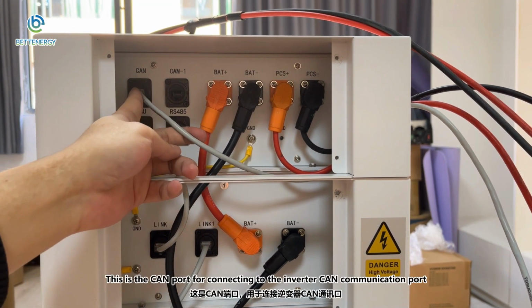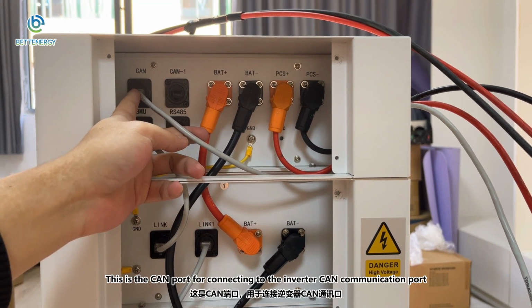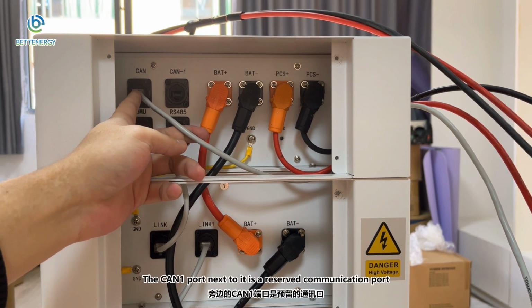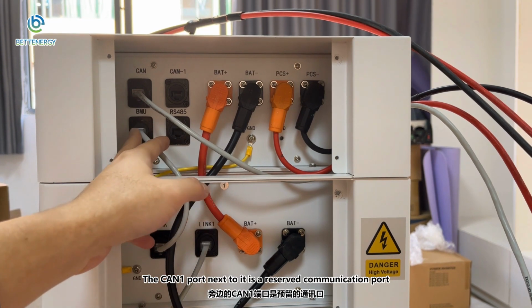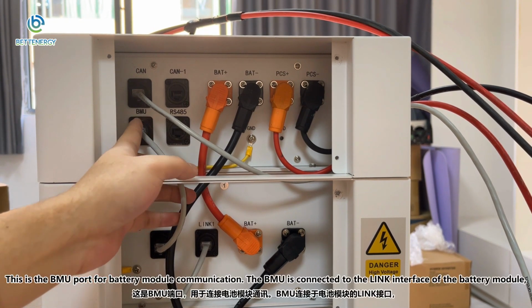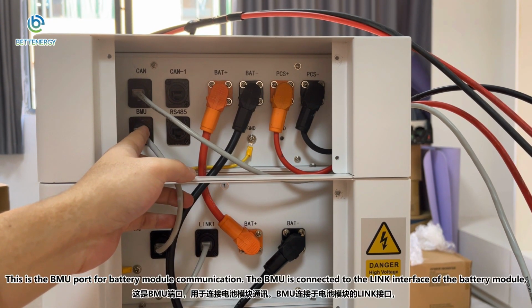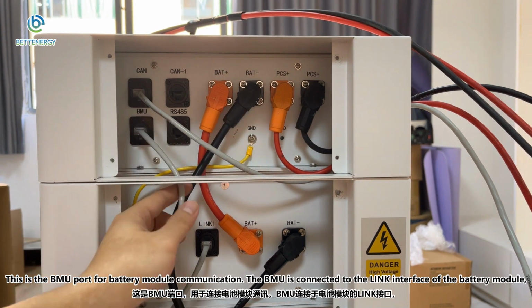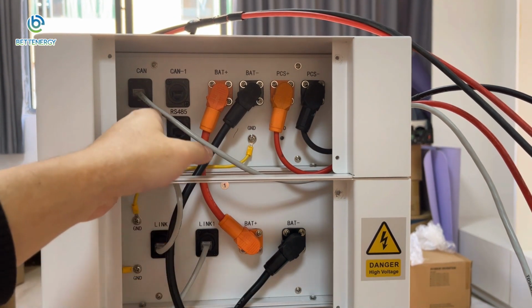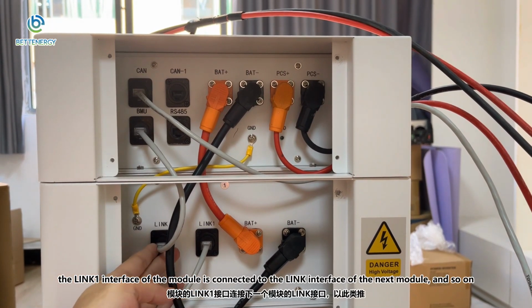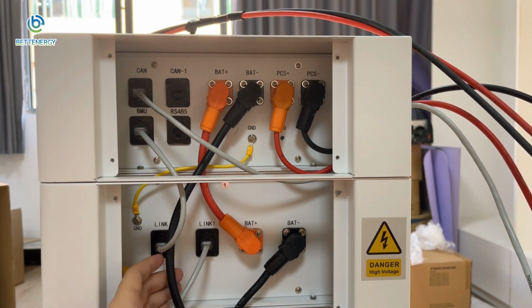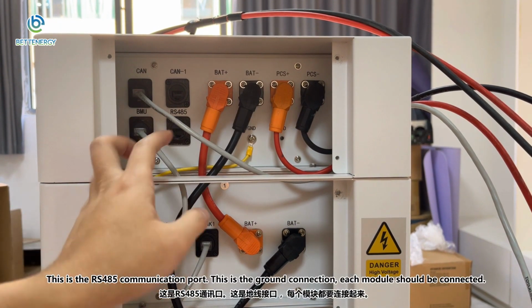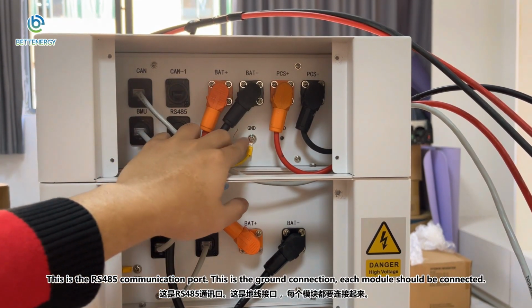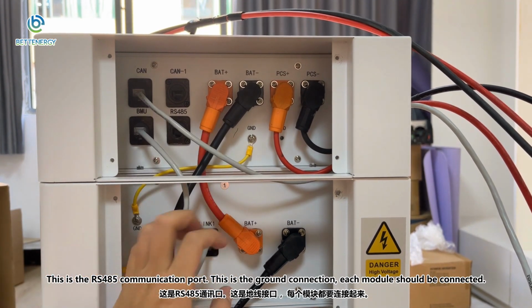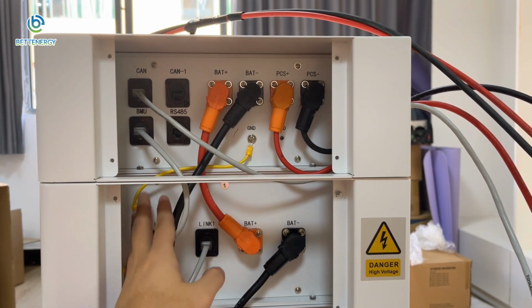This is the CAN port for connecting to the inverter CAN communication port. The CAN 1 port next to it is a reserved communication port. This is the BMU port for battery module communication. The BMU is connected to the link interface of the battery module. The link 1 interface of the module is connected to the link interface of the next module, and so on. This is the RS485 communication port. This is the ground connection. Each module should be connected.